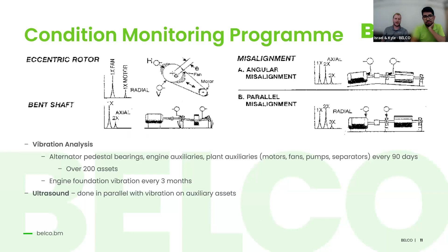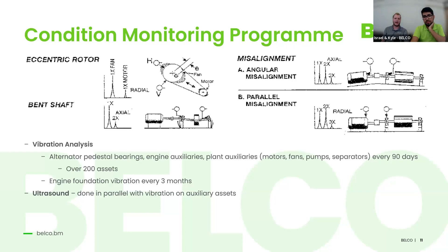So the main part of our condition monitoring program is mostly vibration. We check vibration on multiple pieces of equipment, such as the alternator pedestal bearings, different engine auxiliaries and plant auxiliaries, such as motors, fans, pumps, separators. And we do this on a 90-day schedule. We check over 200 assets plant-wide. And we also use our vibration analysis to check the engine foundation vibration, and we do that on a 3-month cycle. As well as that, we use ultrasound, and we do that in parallel with our vibration measurements, and we generally look at bearing defects with that.